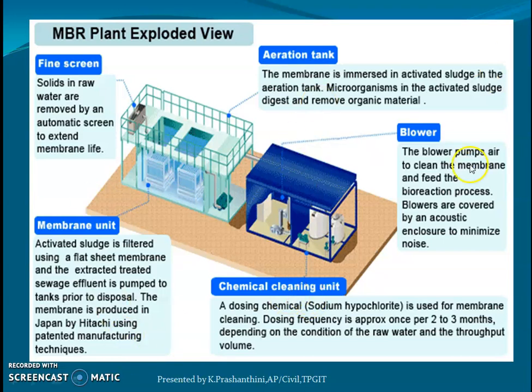The blower pumps air to clean the membrane and feed the bioreaction process. It can be run for every 30 minutes or half an hour. The chemical cleaning unit uses sodium hypochlorite for cleaning the membranes, with a dosing frequency of approximately 2 to 3 months.